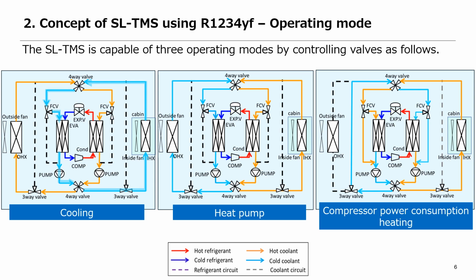In the cooling mode, cold coolant flows through the evaporator, cooling the interior air via the inside heat exchanger. On the other hand, hot coolant moves through the condenser, transferring its heat to the outside air via the outside heat exchanger. In the heat pump mode, hot coolant circulates through the condenser, warming the interior air via the inside heat exchanger. Meanwhile, cold coolant flows through the evaporator, absorbing heat from the outside air through the outside heat exchanger.